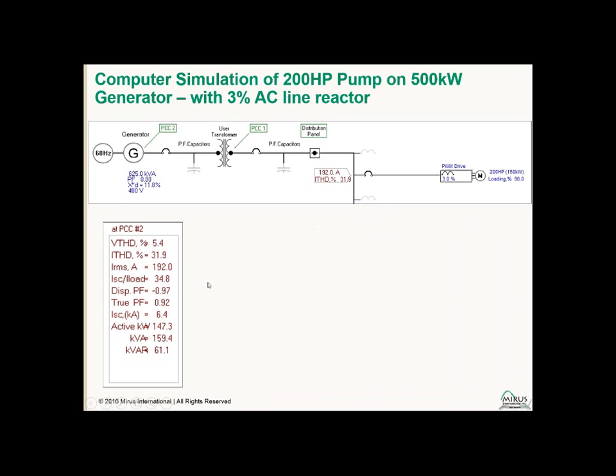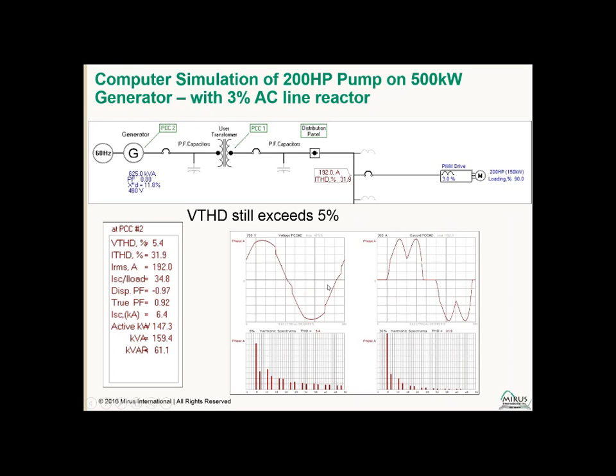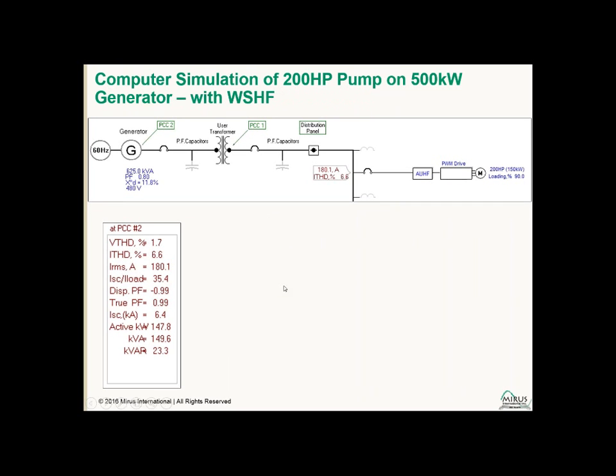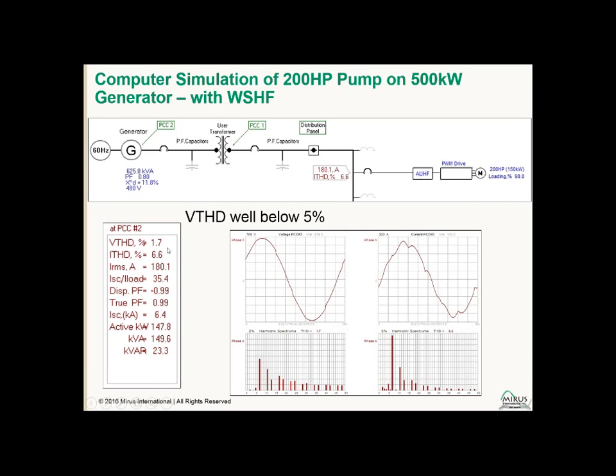When we add the line reactor, current distortion drops, voltage distortion drops as well. Slightly better voltage and current waveforms. When we add the wide spectrum harmonic filter, we can see now our current distortion drops to 6.6%. Voltage distortion is now almost eliminated at 1.7%. Virtually sinusoidal voltage and much more sinusoidal current.